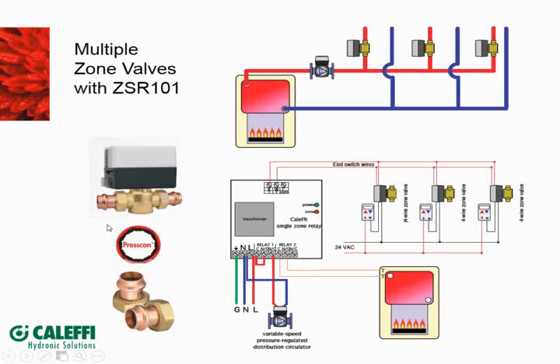Yep. And then also here, in case you guys aren't aware, our Z1 valve now is coming with press fits. We call it the Presscon. We have a few other products as well: pressure differential bypass valves, I think there's a dirt mag, and a 3/4 inch fill valve. But it's a pretty neat product. We're pretty excited about this as well. It has the leak detection, so if you forget to press it and you pressurize it, you'll get a good stream of water coming out of it, so you know that you need to go back and press that one. Yeah, we're excited about that. As you can see, it's got union nuts, so you can take the valve and stuff out. Next month, I think we're doing a seminar on zone valves. We'll be talking more about the different families that those tail pieces can be used on, too. But a little teaser there for you.